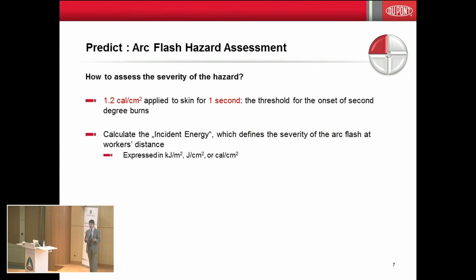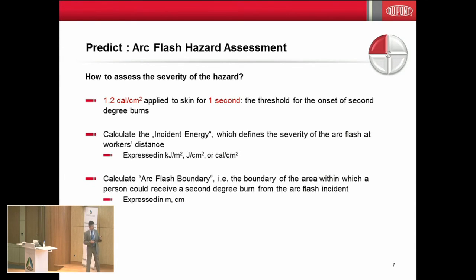At the same time that you evaluate the amount of energy that can come from an electrical equipment, you will have a second element that has to be calculated, called the arc flash boundary. The arc flash boundary for a given equipment is the distance at which, once you pass that boundary, you need to be protected. It has to be defined so that workers understand that once they cross it, they have to be safe from a protection point of view.